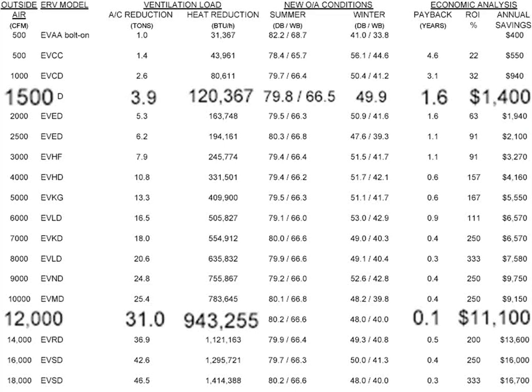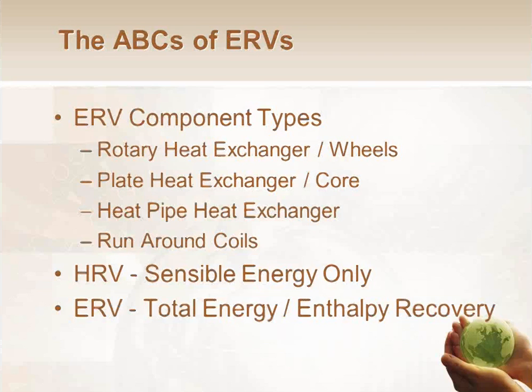The installation for installing the rooftop was not in there because you're already replacing the rooftop. So basically, it's just the incremental costs. I was going to put in, for example, a 50-ton rooftop and replace it. Now instead, I'm going to buy a 30-ton rooftop and an ERV, and I'm going to install it, a little bit more work because there's more work to be done, electrical and so forth. So only the incremental cost difference of the labor and the equipment. So hopefully that answers the question, Paige.